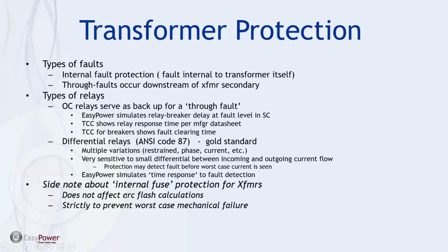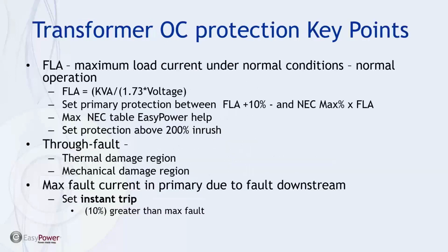It's not for arc flash, particularly downstream protection. So it's basically something that's part of the internal design, and is strictly to prevent worst-case mechanical failure of the transformer itself.